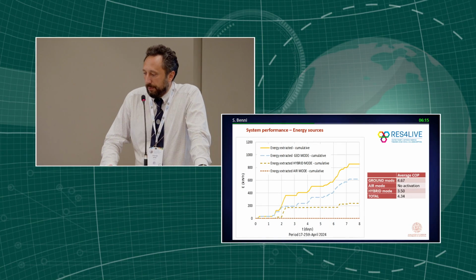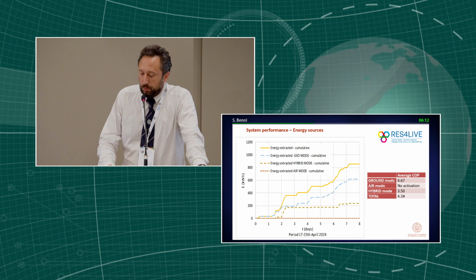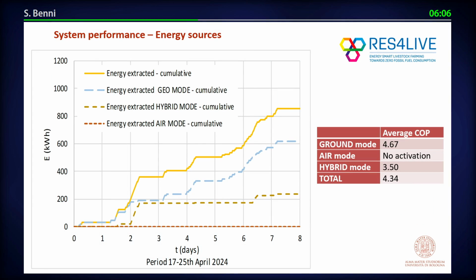And to provide 1,100 kilowatt hours, only 250 kilowatt hours of electrical energy were absorbed. We computed the coefficient of performance of the heat pump, which was totally 4.34, very close to the COP of the heat pump working only with the geothermal source, which is 4.667, a very high value for a coefficient of performance.